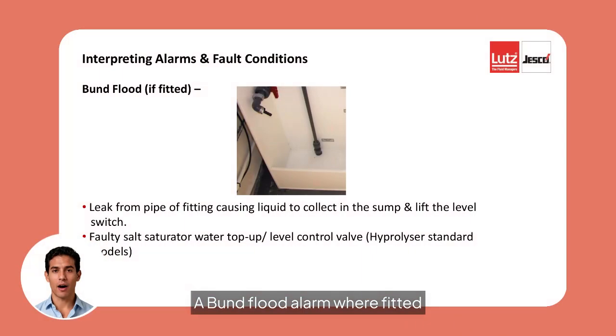A bund flood alarm, where fitted, signals liquid collecting in the containment sump. This may be due to leaks from pipes or fittings, or a faulty salt saturator top-up or level control valve. Prompt inspection prevents environmental contamination and protects surrounding equipment.